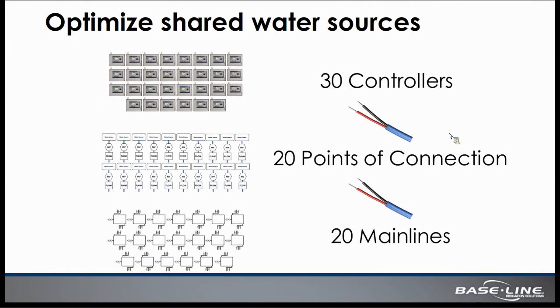So using the two-wire technology, we can ultimately have up to 30 controllers that are sharing 20 points of connection, and we can have up to 20 shared main lines assigned to those 20 points of connection. So in reality and at scale, if the math is done, it gives us the ability, because of the two-wire technology, to manage the operation of up to 6,000 valves at one time.